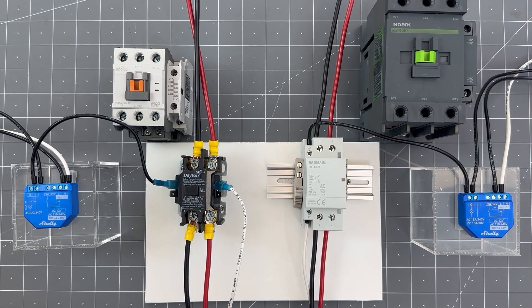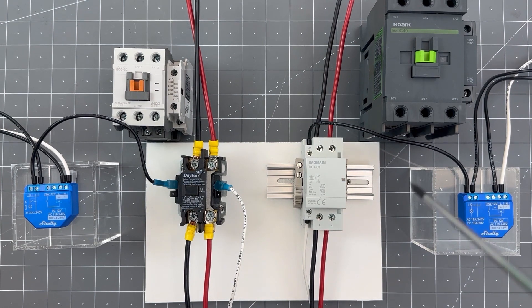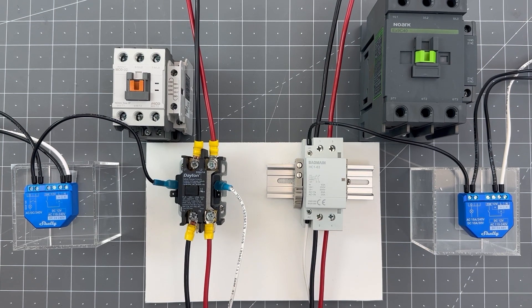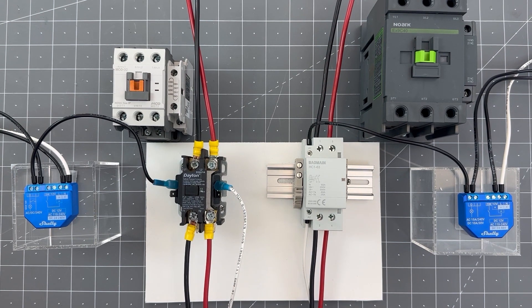Now the DIN rail contactor on the right also has A1 and A2 as you might expect. But notice the incoming line from the breaker panel, those are labeled 1 and 3. The outgoing are labeled 2 and 4 to the device.